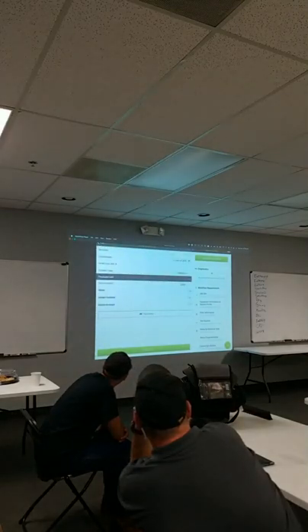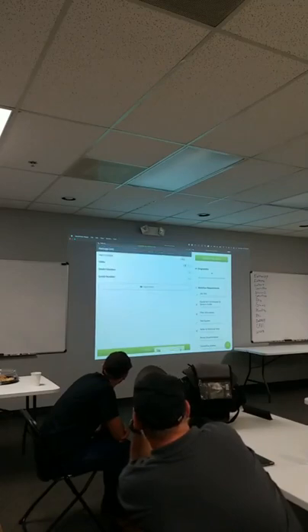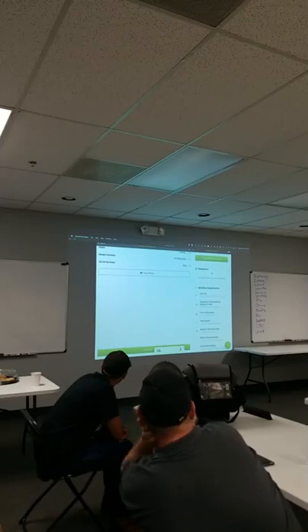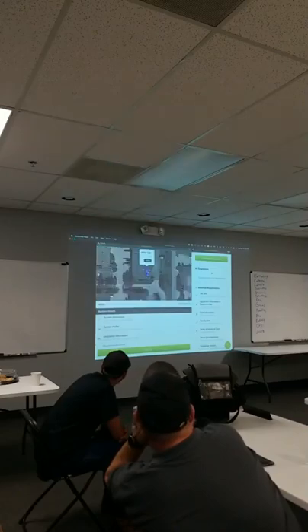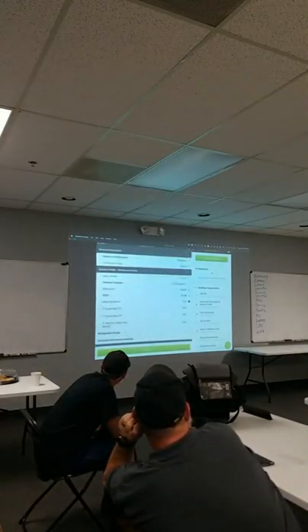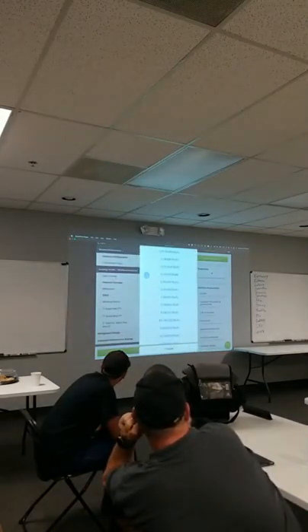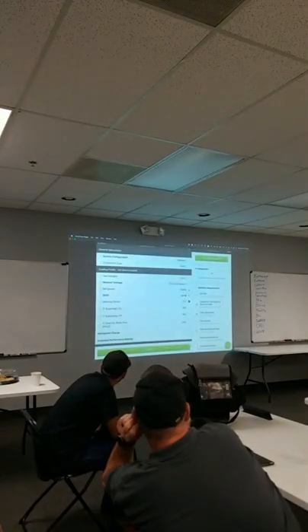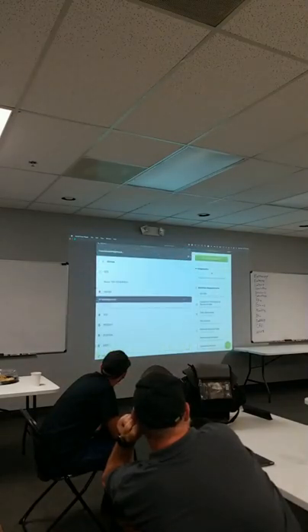We're just putting in its package or split, year installed. We'll say this is just a Trane, and we'll say it's a YCD 090 LOAB. And then we'll just put, let's say, test in here if we want to. And we want to take a photo of the model number, serial number, we can do that also on there. System profile, so this is where we pick up 090 is a 7.5 ton, right? We'd say, in this case here, it's 410A.